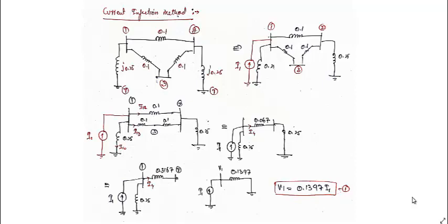First, let us try to find out this when we insert a current source I1 at this bus, and this is the rest of the network, and we assume there is no other source except this I1. This is a little bit of simplification, because this will act as a series from this point to this point. So after series combination, this is 0.2, this is 0.1. The parallel combination will result in 0.067, and 0.25 remains as it is. So this will be 0.067 plus 0.25.